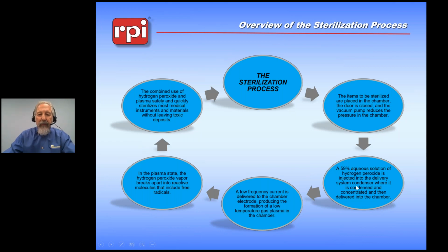Okay, so what are we talking about here? This is the actual cycle that the users will be doing. Again, we talk about how they make sure that the material is in the chamber, that it's pumped down, the aqueous solution of peroxide is put into a vaporizer, and then it's concentrated and delivered to the chamber. We take that peroxide, we apply a plasma to it, or turn it into a plasma using a current generator that's delivered onto the material, and the peroxide breaks apart, and the combination of peroxide and oxygen is what does the sterilization without leaving residue.